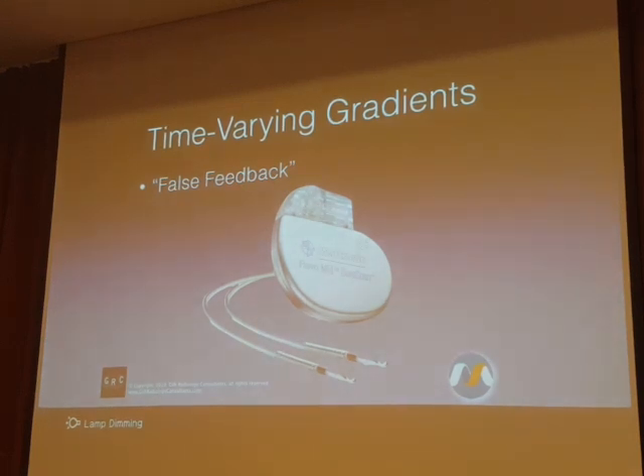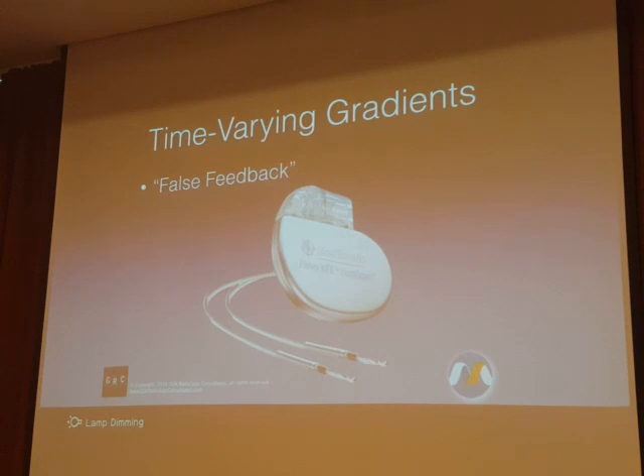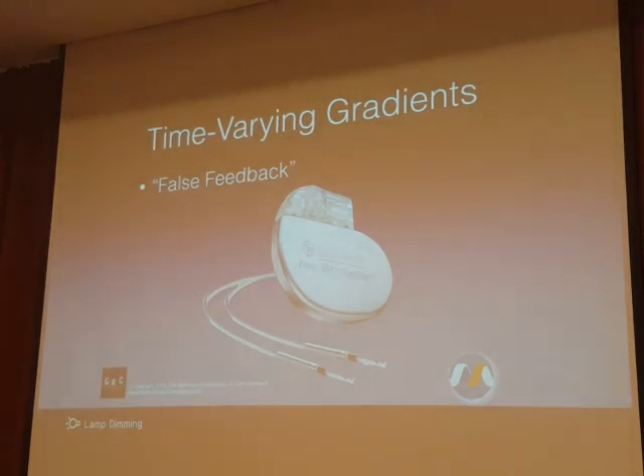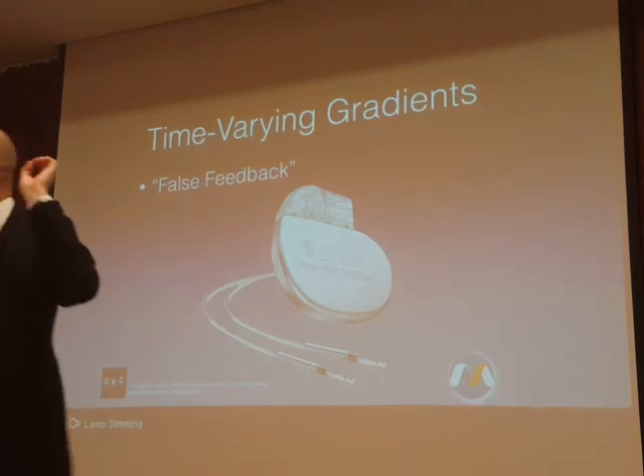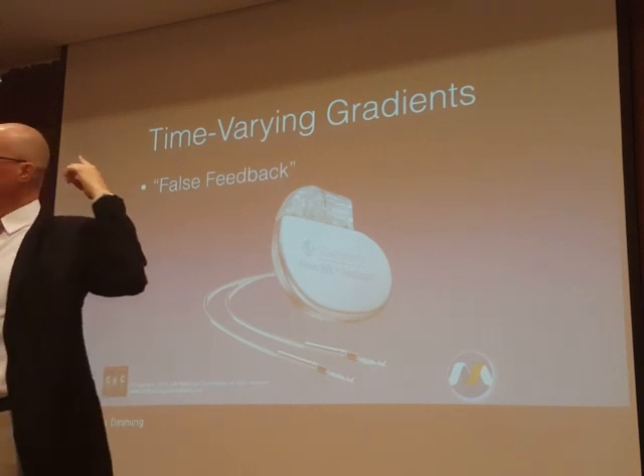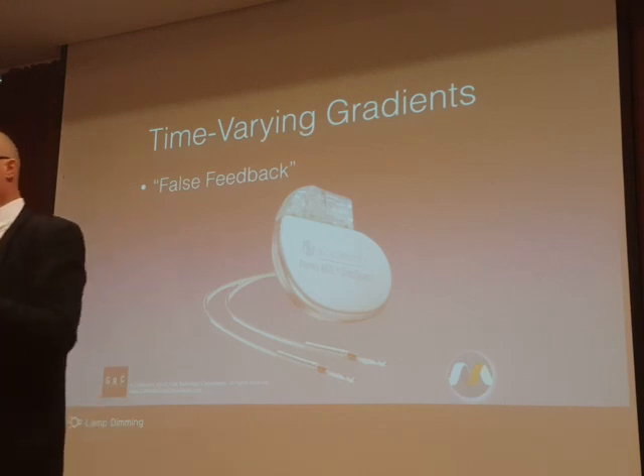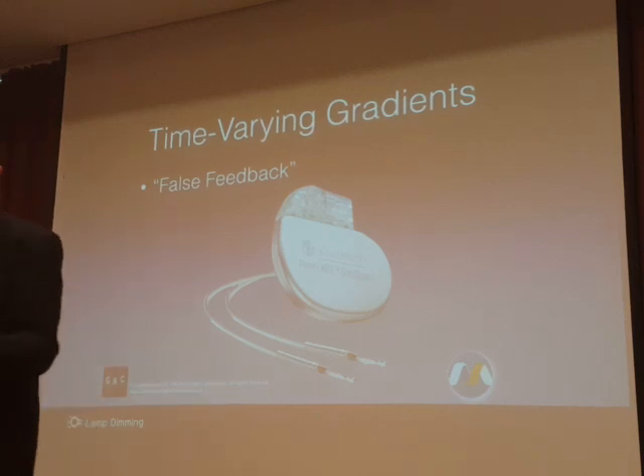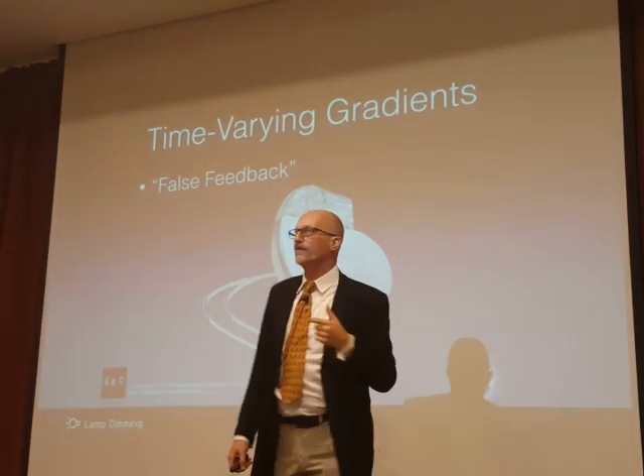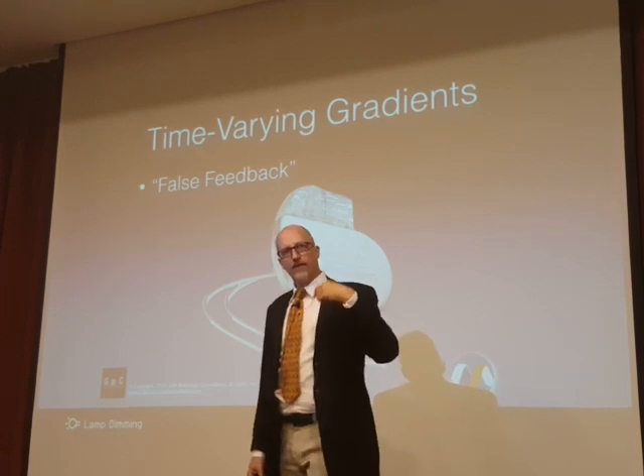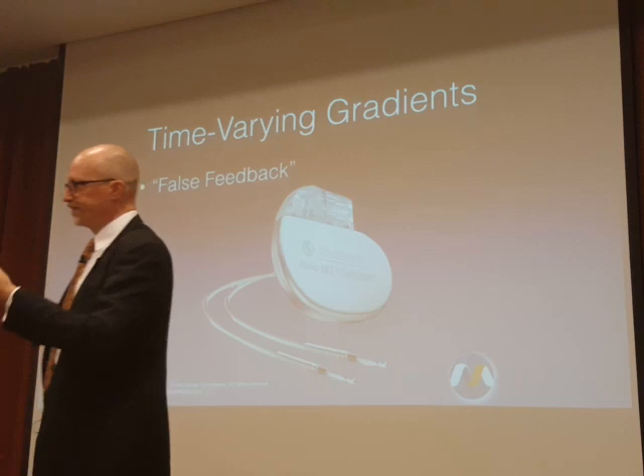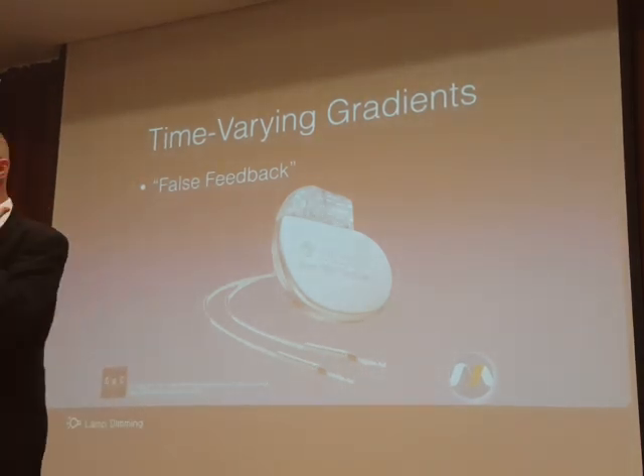If it thinks that the heart is beating many times per second, it will fire many times per second to try and capture that heart rhythm and bring it back down. So it'll start firing at the rate that it perceives the heart is beating, and gradually it'll slow it back down to where it's supposed to be. If it's perceiving the time-varying gradients as cardiac rhythm, and it starts firing in response to the time-varying gradients, it may take a situation where there is no problem and create a problem. So false feedback of gradients, rhythmic gradients, producing an erroneous assumption on the part of one of these devices is a real potential.